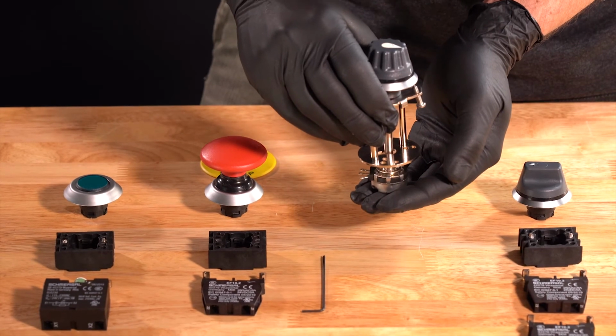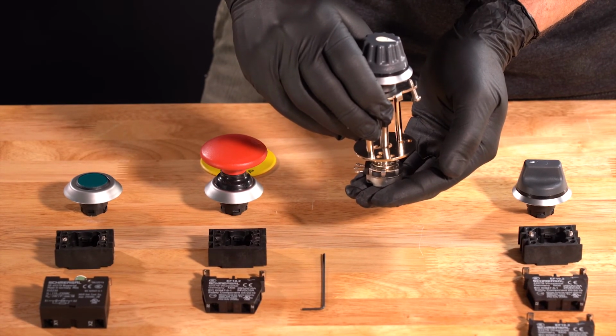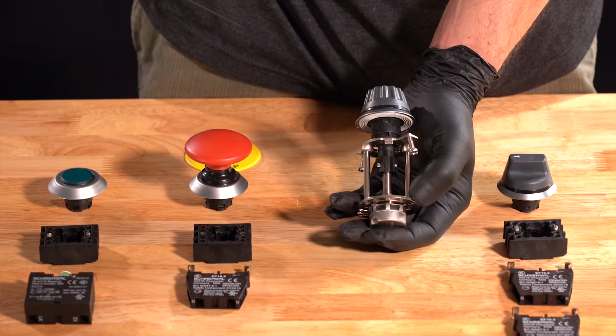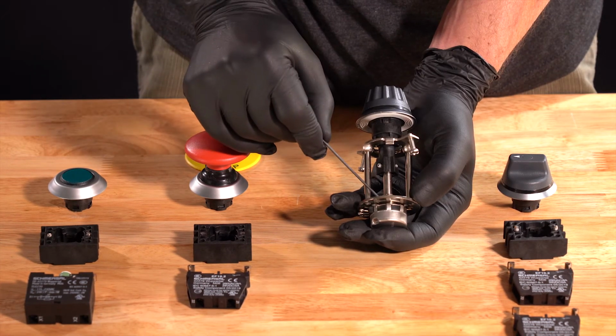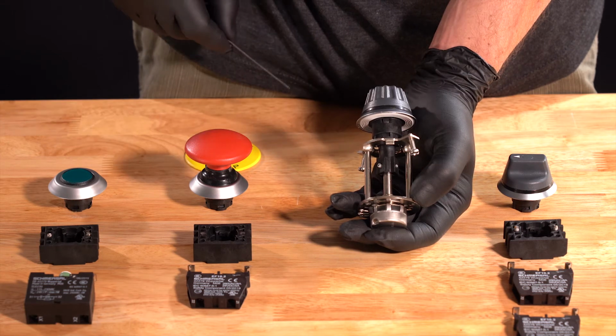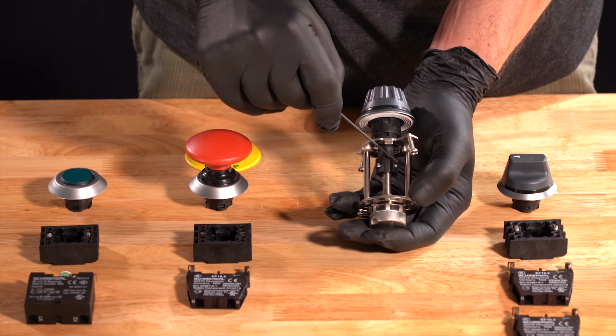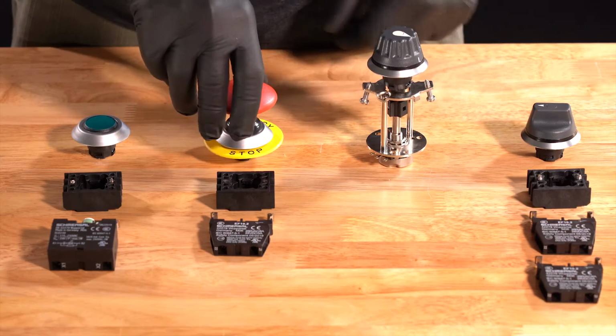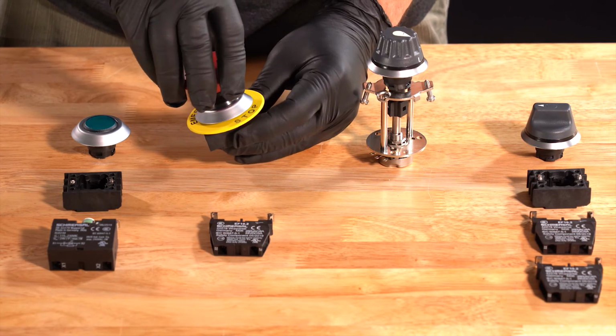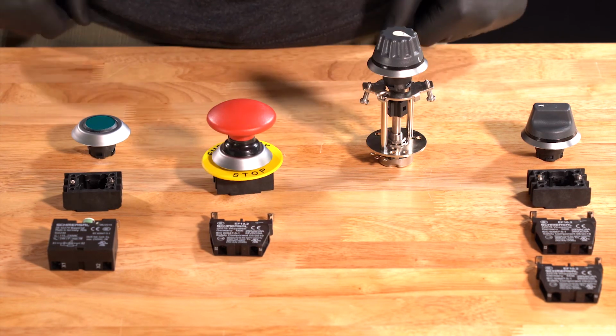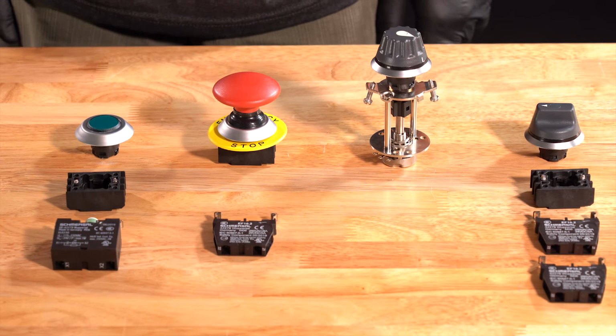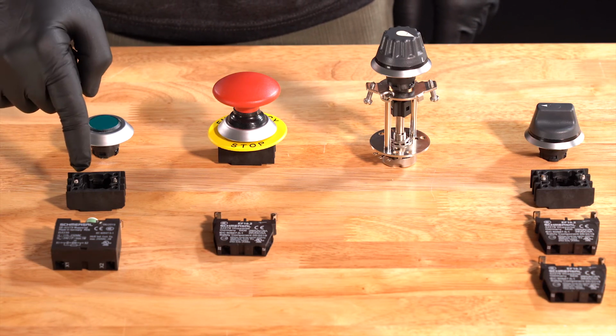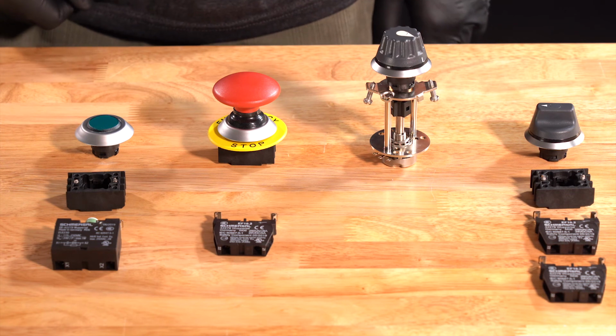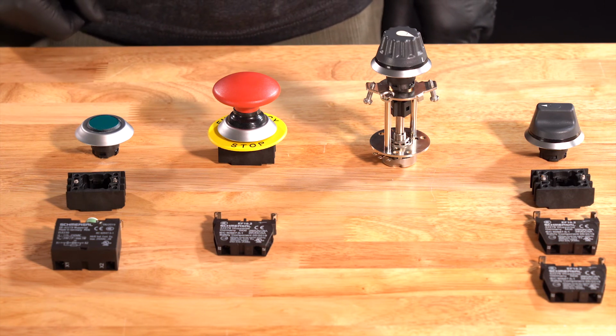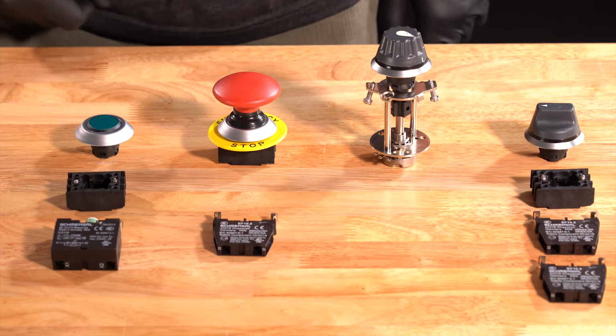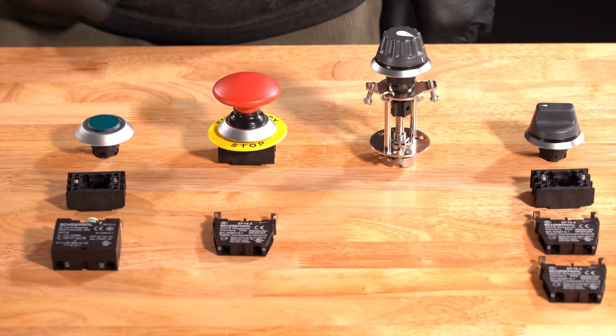With orientation established, you can insert the potentiometer shaft into the bottom of the dial. After securing the potentiometer to the mounting base with the nut and washer, you're going to want to set the 2 set screws on the shaft with a 1/16 hex wrench. The E-stop button inserts into the mounting base with a 1/4 turn. The contact block simply snaps on. Lastly, the light mounts into the base in the same way. A 1/4 turn will secure it to the mounting base. Notice that the bulb is located in the contact block. If you ever need to change a light bulb, it would take place from inside the panel.